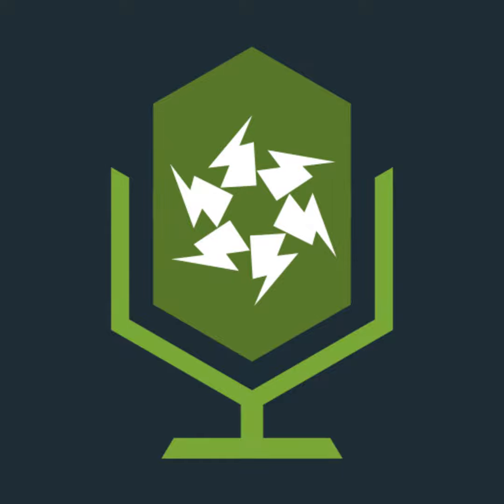In chapter 53, we're going to look at selection and erection of types of devices, and different types of devices have different purposes. So we're going to look at the need of devices for protection, the need for devices for isolation, a switching device, a control device, and a monitoring device. Now, they're all different devices, but if you think about those words specifically, you can understand how they are all important and how there will be certain requirements for each consideration. With protection, we'll obviously be thinking about protection against electric shock and protection against fire. Isolation we've already mentioned previously in the video: methods of switching, which were for isolation, mechanical maintenance, or emergency switching. We also had functional switching, and we had control switching. So we're going to go through these here.